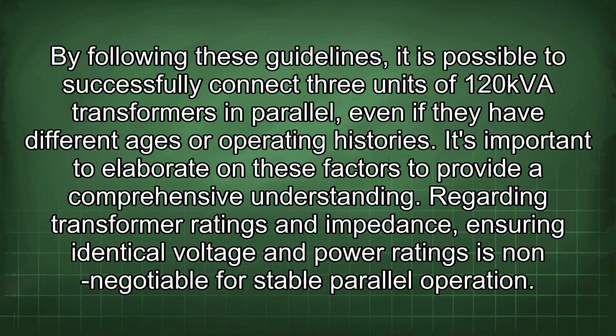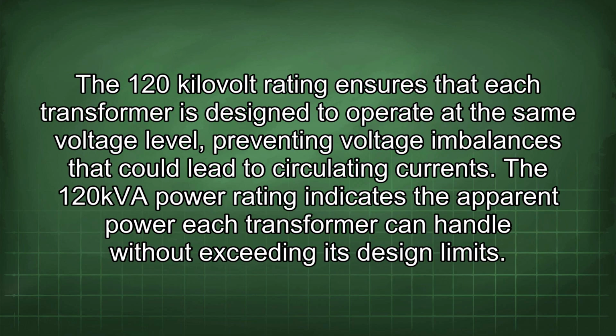Regarding transformer ratings and impedance, ensuring identical voltage and power ratings is non-negotiable for stable parallel operation. The 120 kV rating ensures that each transformer is designed to operate at the same voltage level, preventing voltage imbalances that could lead to circulating currents. The 120kVA power rating indicates the apparent power each transformer can handle without exceeding its design limits.